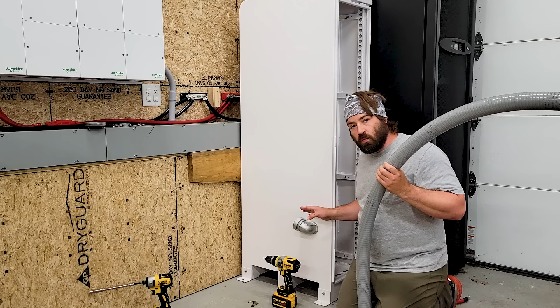We have our 2-inch 90-degree fitting on the cabinet, and the conduit's going to come this direction and then up towards those bus bars on the wall. I screwed on this piece of scrap 2x material to give me something to fasten the conduit to. This is a flexible watertight conduit, and between the fitting, the conduit, and these brackets, it was about $60 at my local electrical supply house.